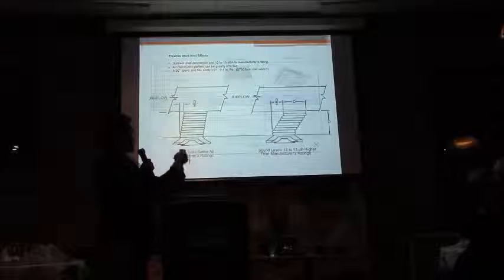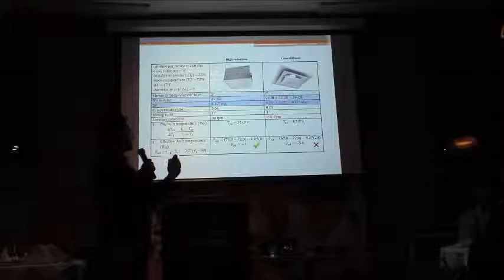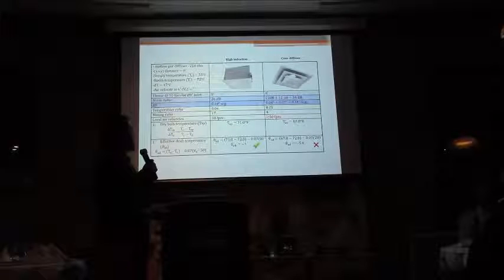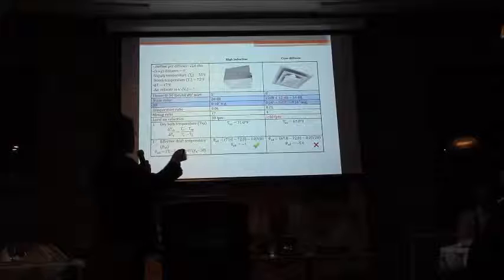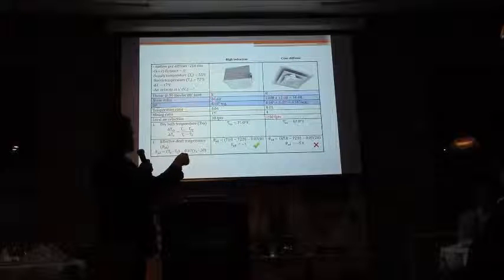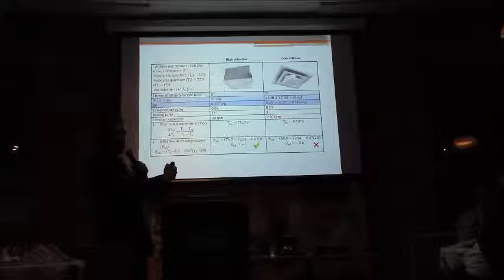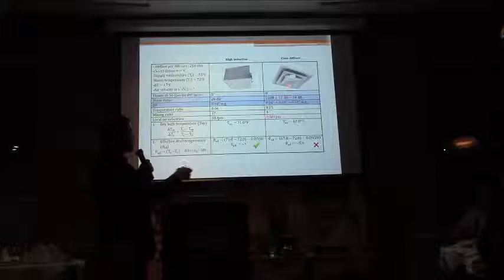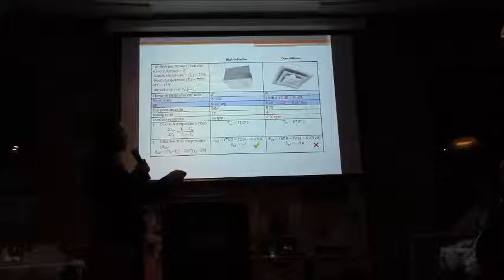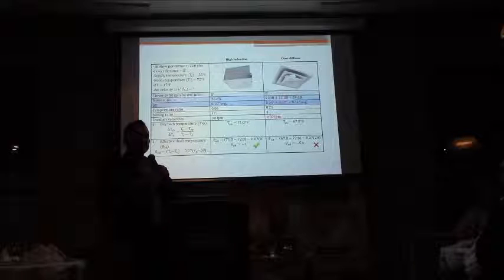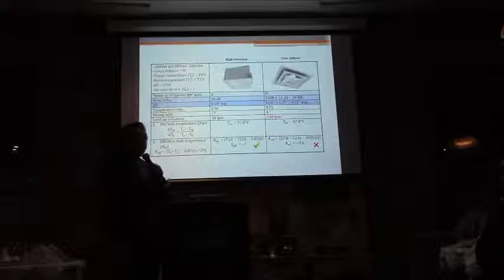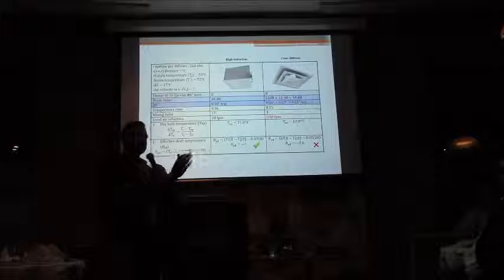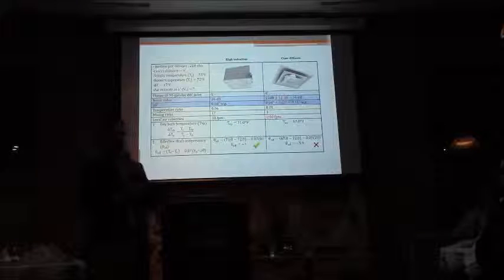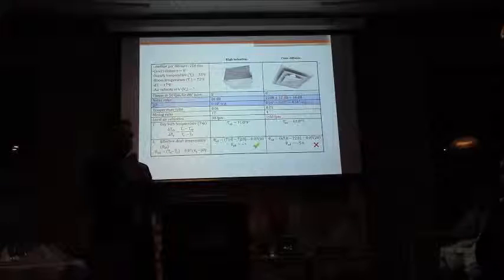So let's see what all that does. Exactly the same table that I showed you previously. Let's see what all these things do to the values we have. Like I said, the throws don't change, but the noise values, we're at 26. It stays at 26 because of the plenum. While this one can go up to 34 decibels, unless you're using a plenum with the cone diffuser. If you are, you won't have any problem. The plenum is not exclusive to high induction. For any diffuser, if you use a plenum, you know that you're going to have whatever rating the manufacturer gave you at the design phase.